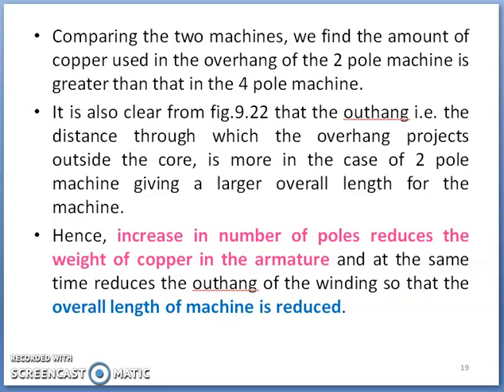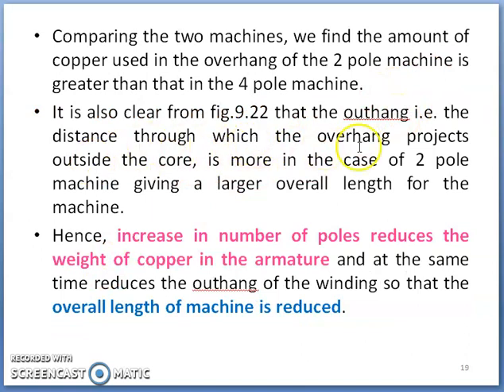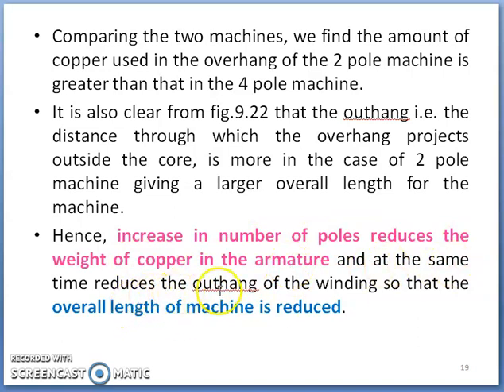This is an advantage. The amount of copper used in the overhang of a two-pole machine is greater than that of a four-pole machine, because the overhang distance through which it projects outside the core is more in the case of a two-pole machine, giving a larger overall length. Hence, an increase in number of poles reduces the weight of copper in the armature and at the same time reduces the overhang of the winding, so that the overall length of the machine decreases. Increase in number of poles will reduce the requirement of copper in the armature section.